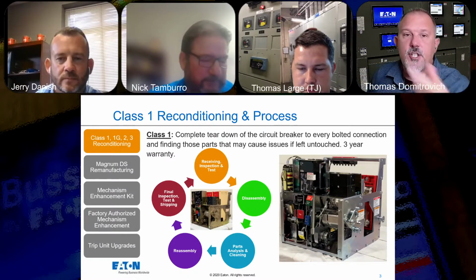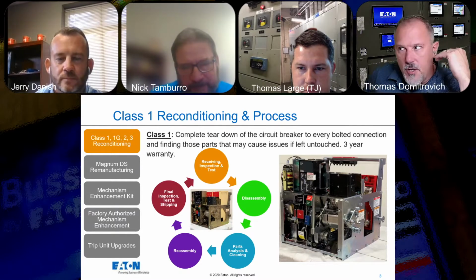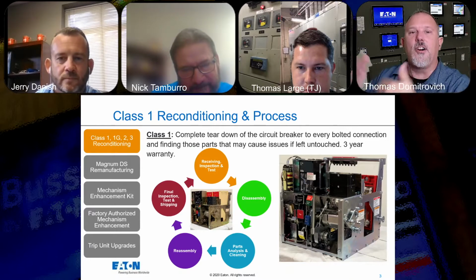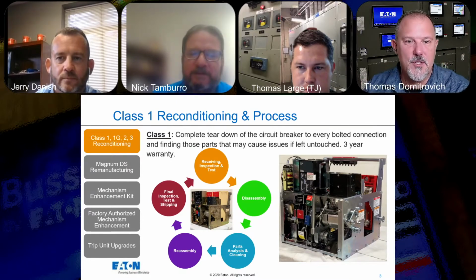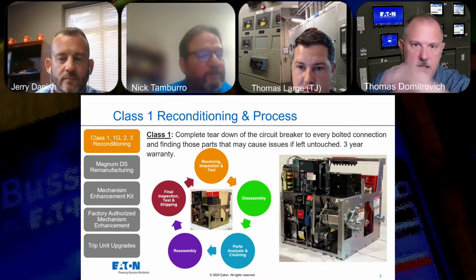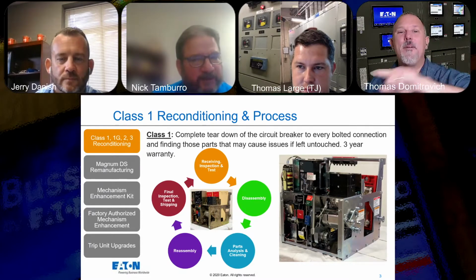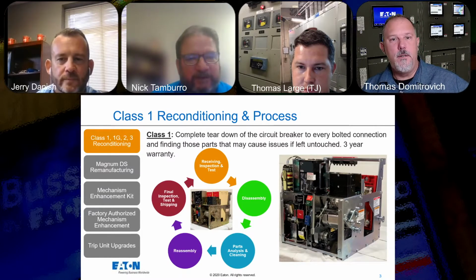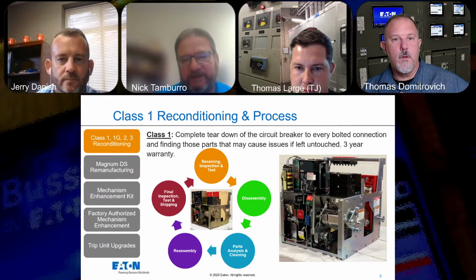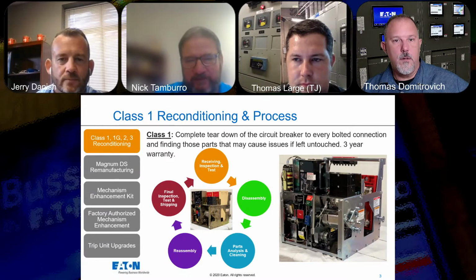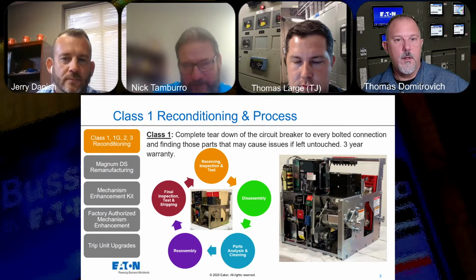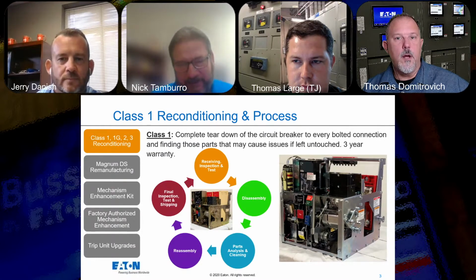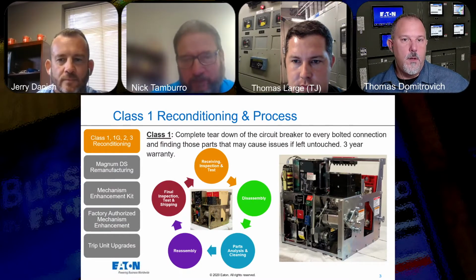How much current do you put through it to get it to trip? I mean, you don't put 100,000 amps through it, right? Oh, you're talking about primary injection testing or electrically operating? Primary injection testing. For a DS breaker with a 10 series trip unit, it's based off the CTs, the rating plug, and the settings of the trip unit. So you get a DS 416 with 1600 amp CTs and a straight rating plug, which I mean is a 1600 rating plug with 1600 amp sensors. Because on the DS and DS2 retrofit kits, you can have 1600 amp sensors but a 1600/800 amp rating plug. People will do that for coordination purposes.